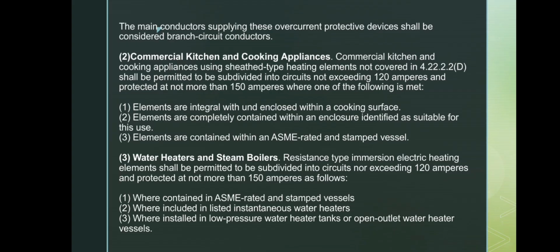For water heaters and steam boilers, immersion type heating elements may also be subdivided into circuits up to 120 amperes protected at no more than 150 amperes when they are installed in ASME rated vessels, part of listed instantaneous water heaters, or installed in low pressure or open outlet water heater tanks.